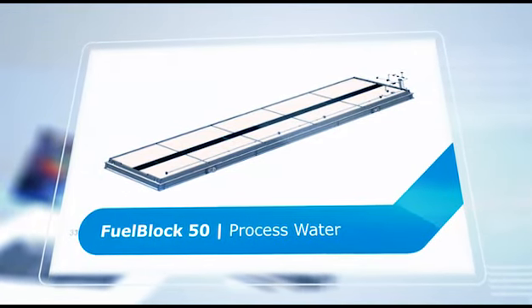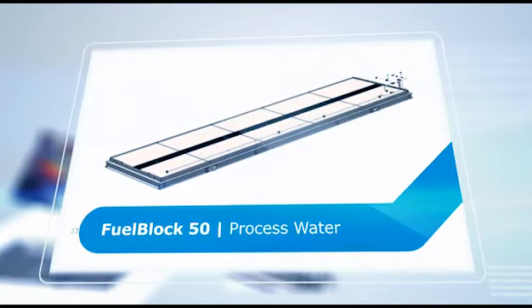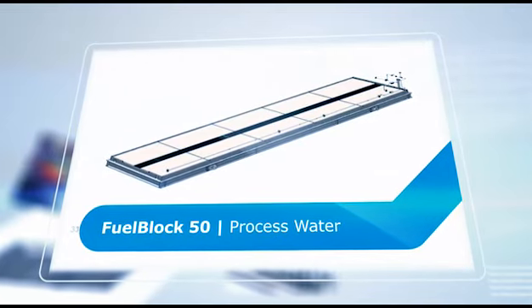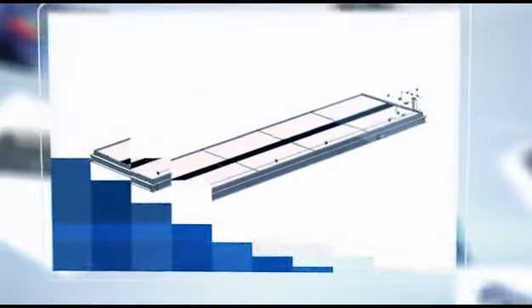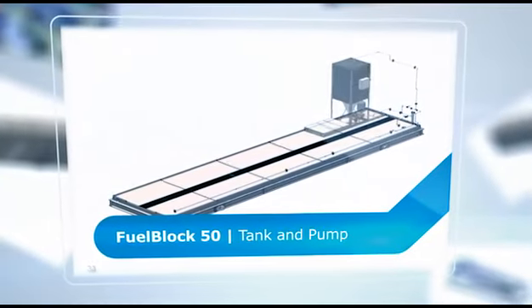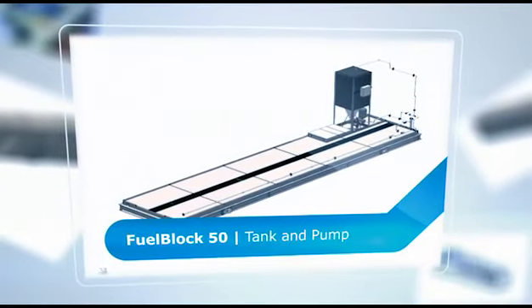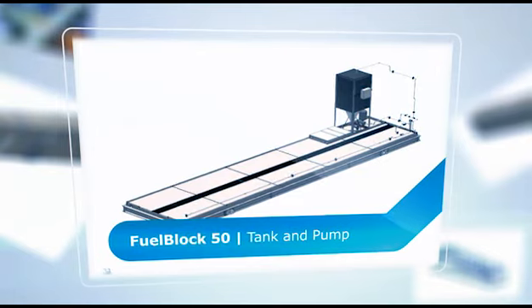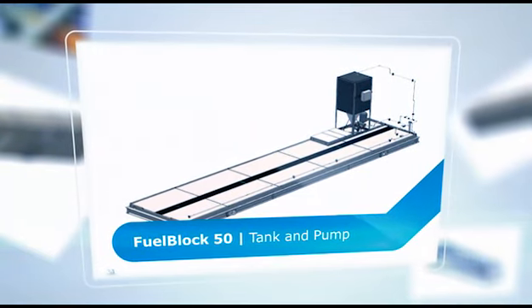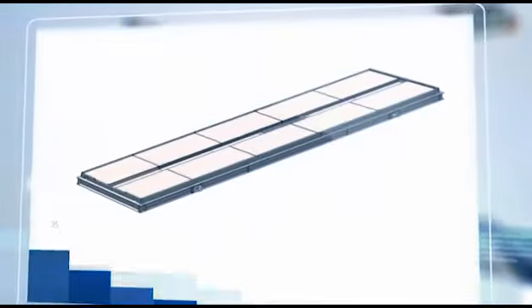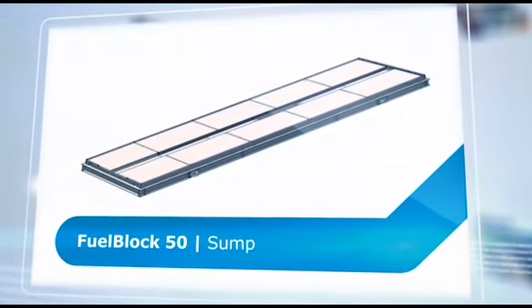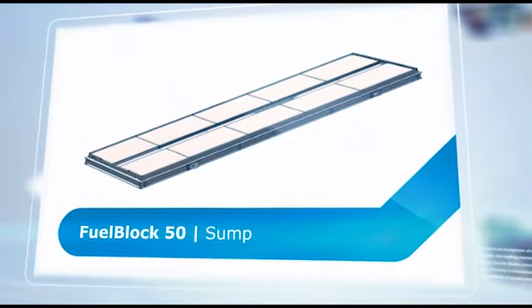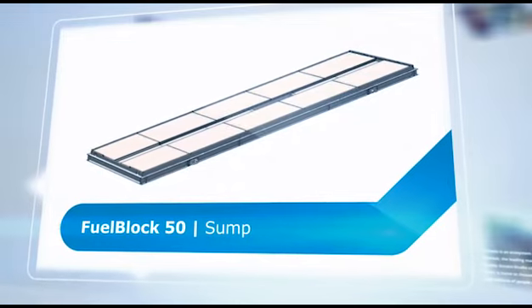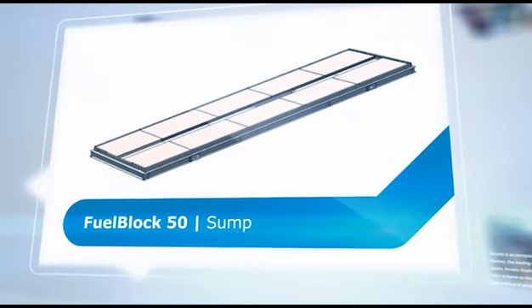A cartridge depth filter is provided to remove particulate matter from the process water. A 2,000 litre storage tank, pressure pump and accumulator can be provided for sites without a process water system or with intermittent supply pressures. Centrifuge heavy phase waste, bowl discharge fluids and fluids recovered from the last chance filters are received in the common sump of the fuel block.